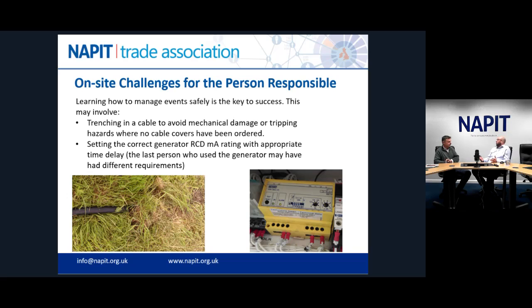It doesn't differ from traditional understandings of selectivity or what used to be discrimination. It's just that some of the viewers may not be familiar with adjustable RCDs and time delays. There's an application for such devices in events, because quite often you won't actually know what the loads are, and so you won't know what the leakage currents are. So there is an element of setting them up on the hoof. And so it's important to be able to measure these things, or at least set them to reasonable levels so that you don't get unwanted operation. And the senior person responsible would be responsible for ensuring that the correct coordination was in place.